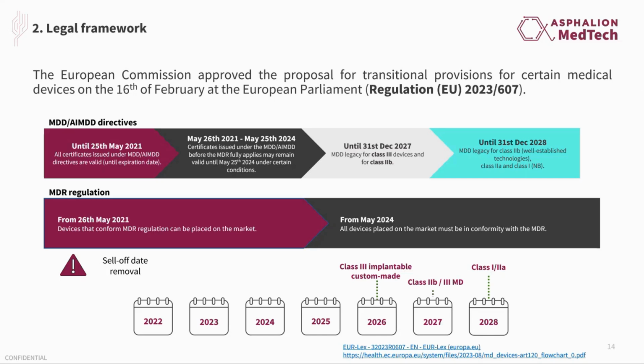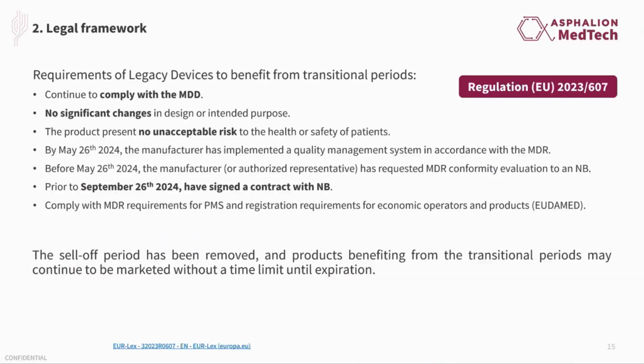For those devices that were previously approved by the directives, they also have to be certified under MDR according to the timeframes given by the European Commission for this transition, considering the transitional provisions for certain medical devices as defined in Regulation 2023/607. In order to benefit from the transition periods of this regulation, legacy devices must comply with all these conditions. They continue to comply with the MDD, no significant changes, no unacceptable risk, and we would like to highlight the fact that it is mandatory to already have a signed contract with a notified body for the transition to MDR.